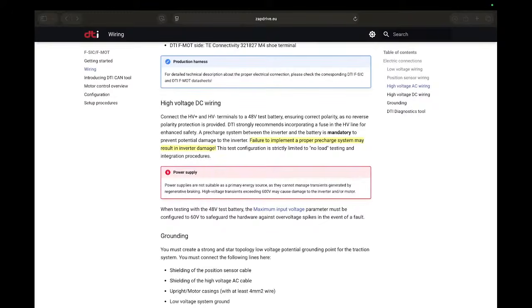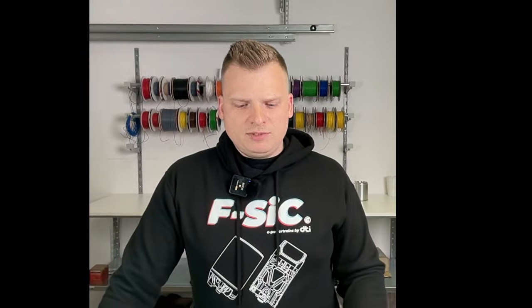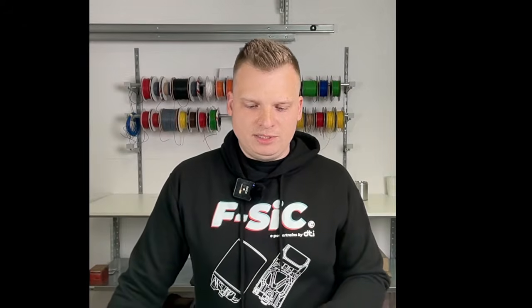So fuses are also needed externally from the inverter. Some teams are using separate fuses for each inverter block, or you can use even one bigger one, but it should be separated from each other. So each block should have a separate fuse inside.